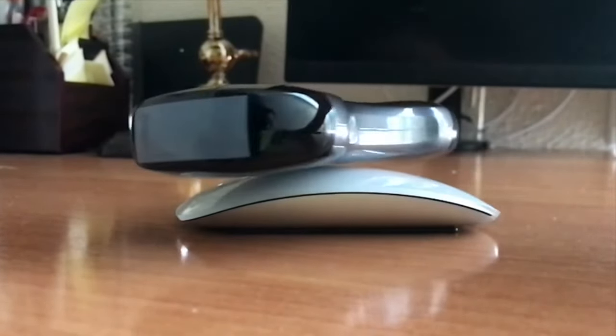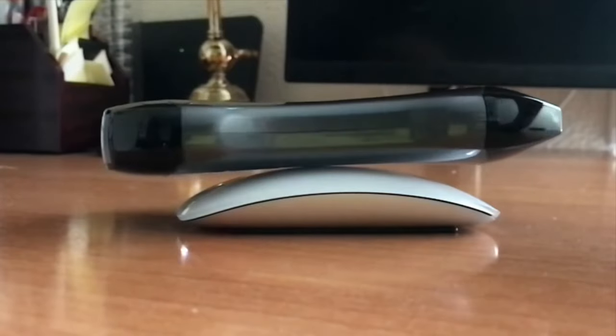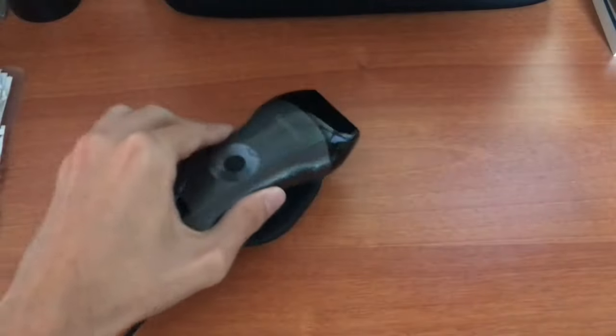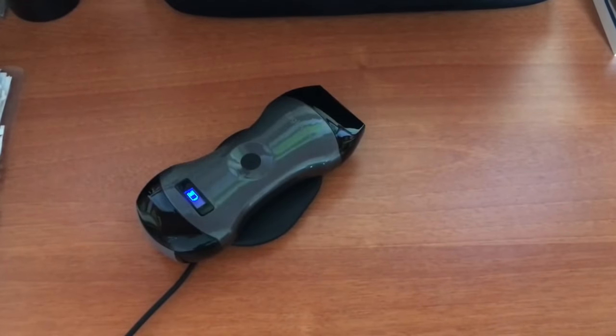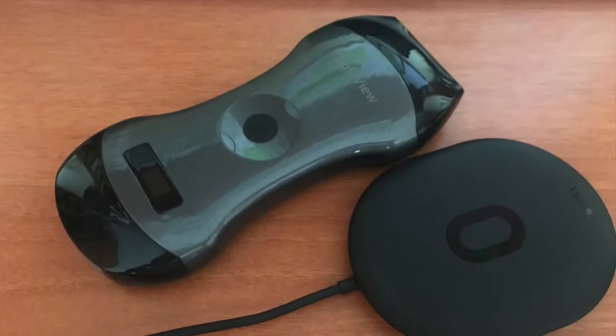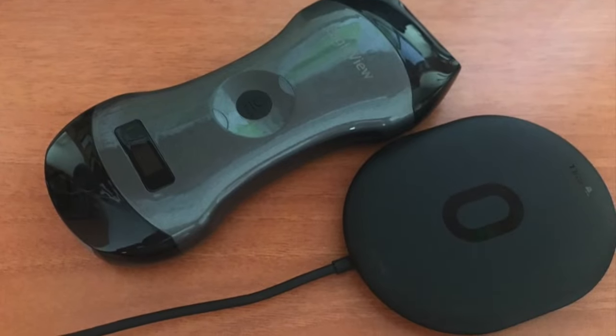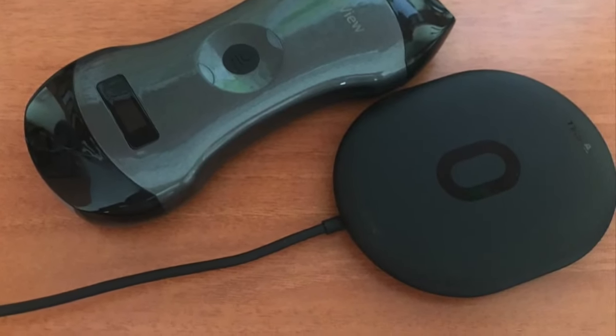As I've been testing it intensely, I must admit I used Color Doppler for quite long periods. The official webpage states between 3 and 5 hours of total time. Simply placing the device over the wireless charger that comes in the same box will recharge the battery. In my case it required approximately 2.5 hours for a full charge, although they claim less than 2 hours on their webpage, and it cannot be used while charging. It has no ports — everything is wireless, including charging and exporting images.